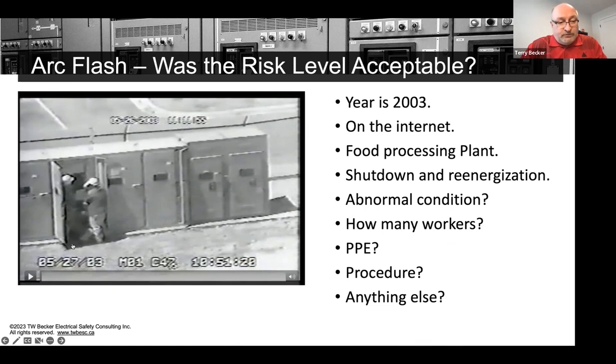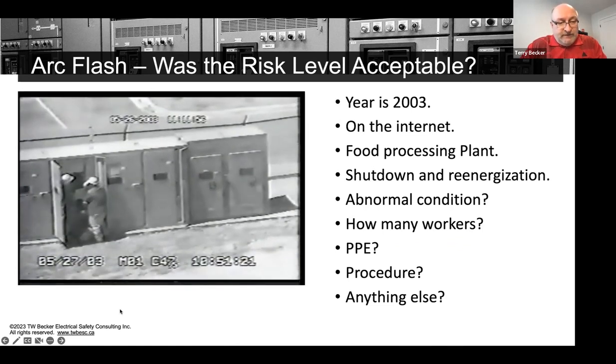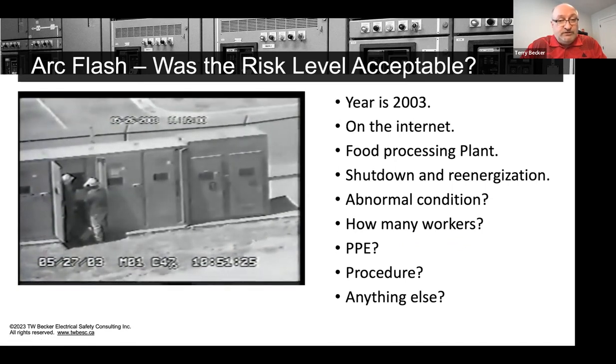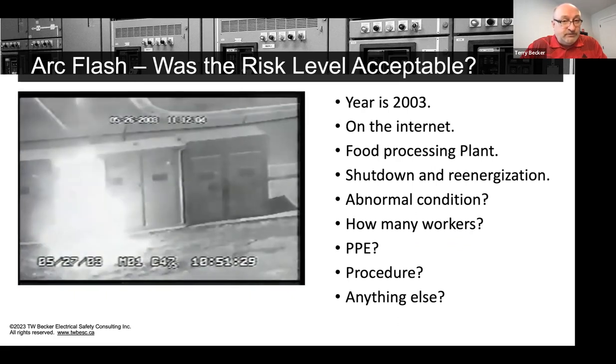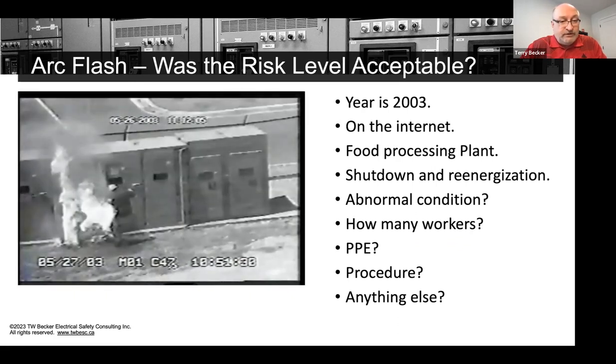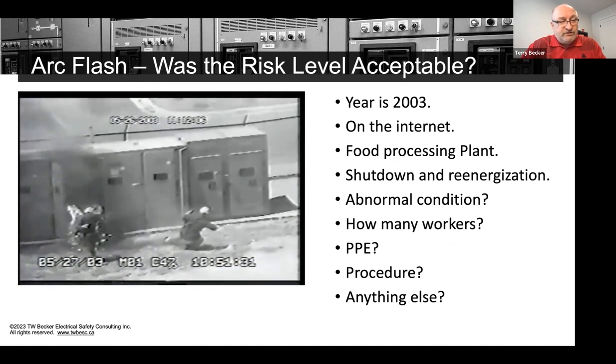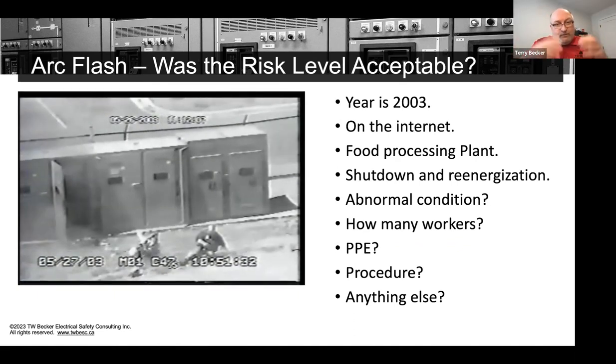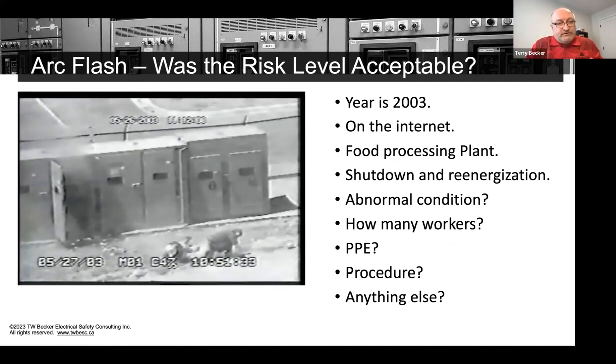There are three workers here. There's a worker on his back. There's no sound, so something happens. He's interacting in high voltage switchgear, outdoor, 13.8 gear. He's in a cell that probably has low voltage in it, and somehow creates an abnormal arcing fault. You see the arc flash, the plasma, and then it went away quickly because it was cleared by an electrical protective device.